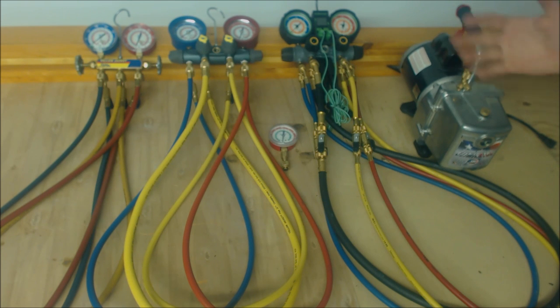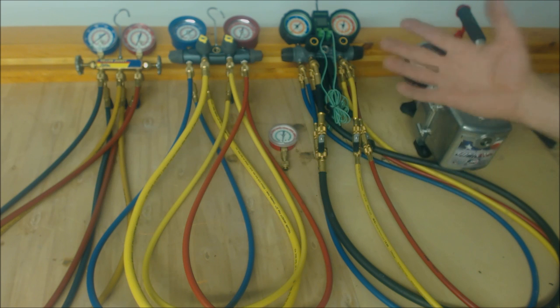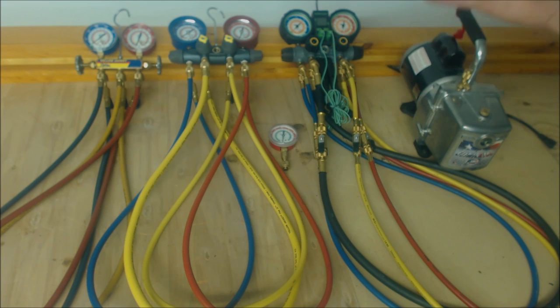This is a JB. I like JB vacuum pumps, always have. I've used Robin Air and Yellow Jacket in the past and JB makes a real good vacuum pump. This is the eliminator. There's ones with gas ballast and then also your on off valve. This one doesn't have either of those. This is a little bit less expensive of a model but it really does the job very well. You want to make sure that you're always changing the vacuum pump oil in these. Otherwise the seals will not work very well. Especially when you are vacuuming out a very contaminated system, you really want to change the oil on that. Otherwise the whole vacuum pump will be bad, at least the front here at least, not the motor, but the front will be bad if you don't change the oil. And it will not be able to pull a 500 micron vacuum or getting down to 200 microns or lower and then allowing the system to rise up to below 500 microns.